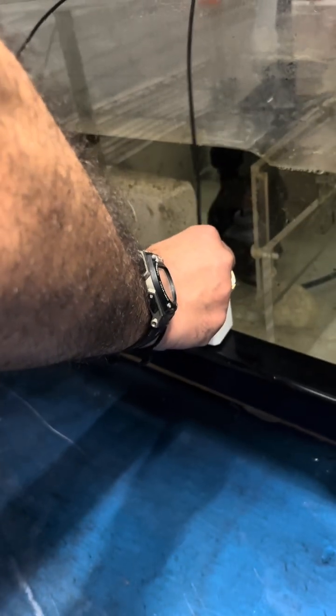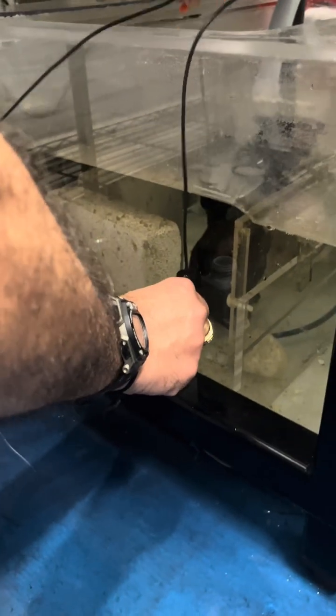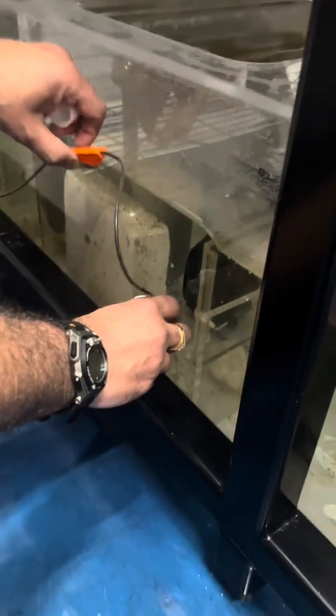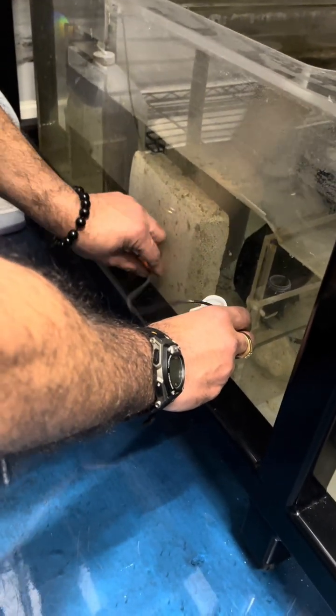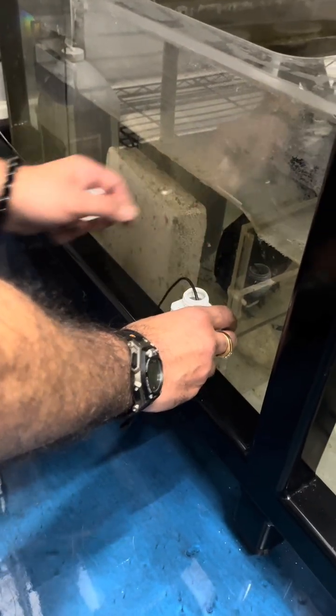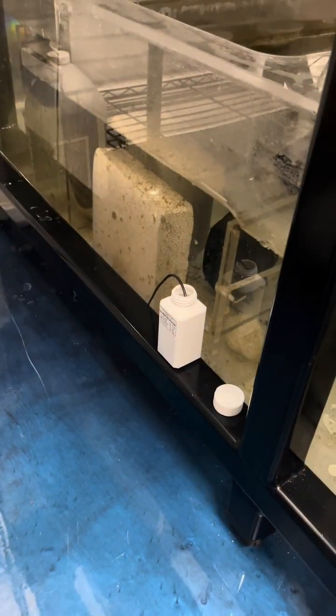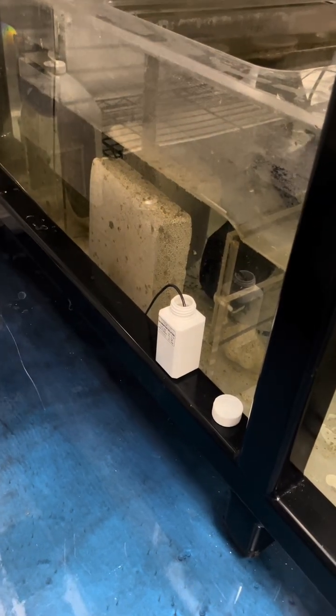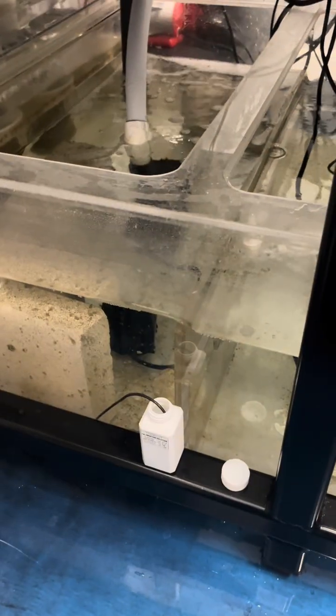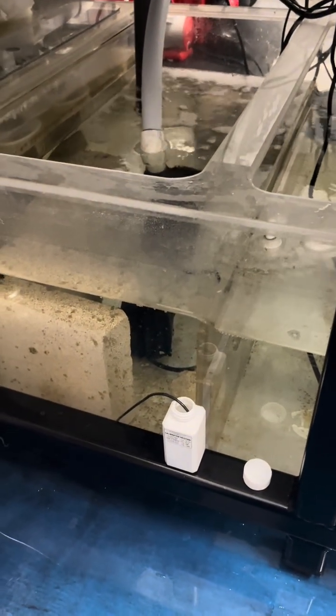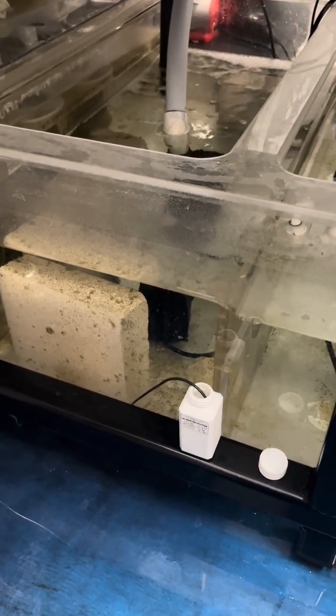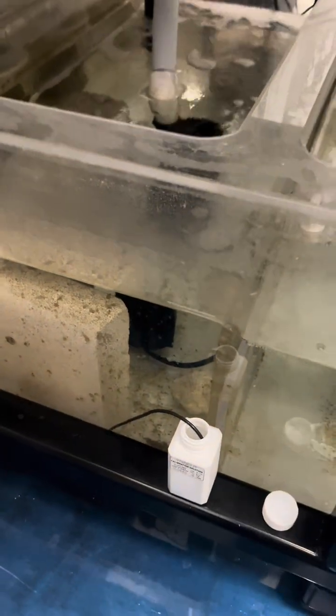Now, make a note that you get 1 bottle of this calibration liquid in the Trident box, but you are supposed to use it only 1 time. After each use, when you finish your calibration, you have to throw it out, and for your next calibration, whenever you need to, you have to have a new bottle. So now we'll go back and get these values put in the software and get the calibration started. The calibration usually takes around 40 to 45 minutes, where it will keep testing each and every additive: calcium, magnesium. So let's go ahead and get the process started.